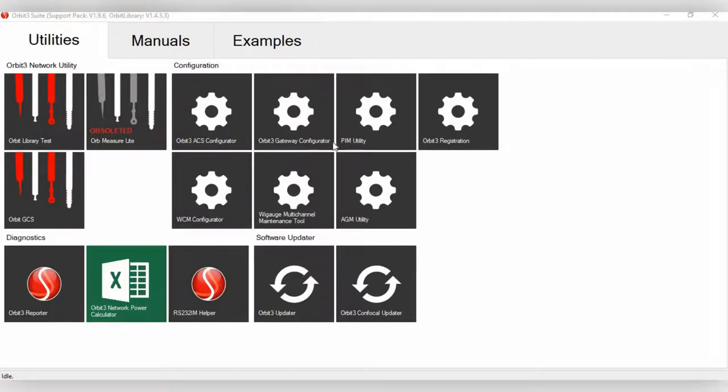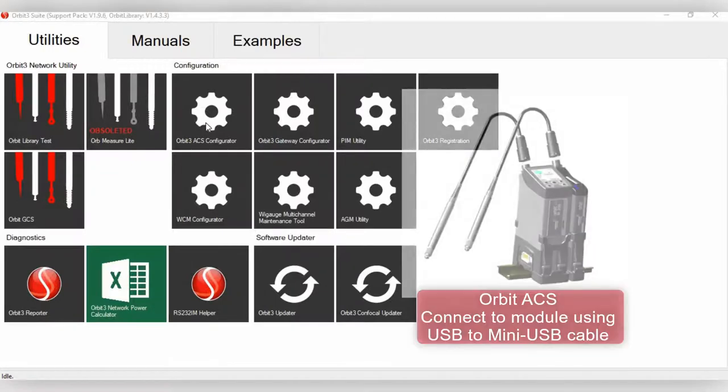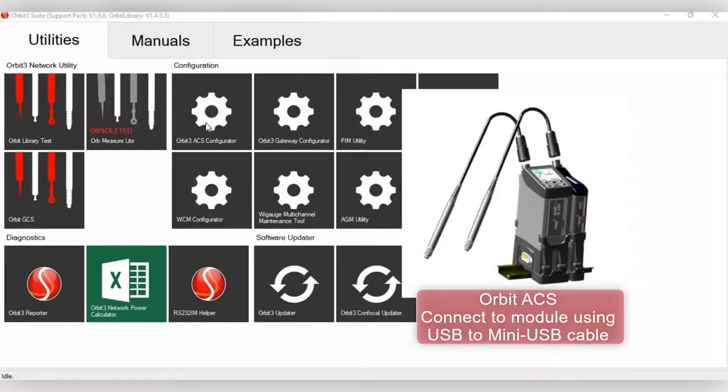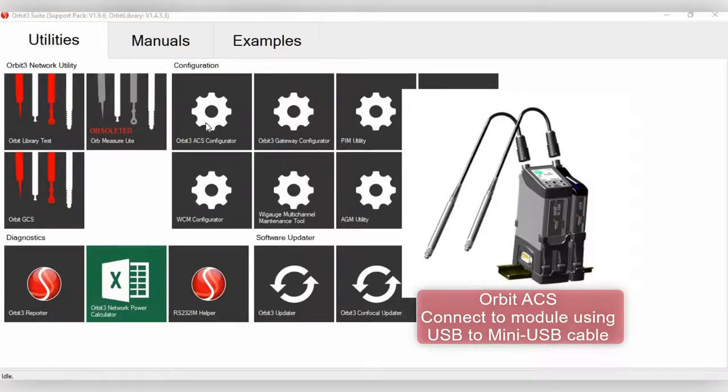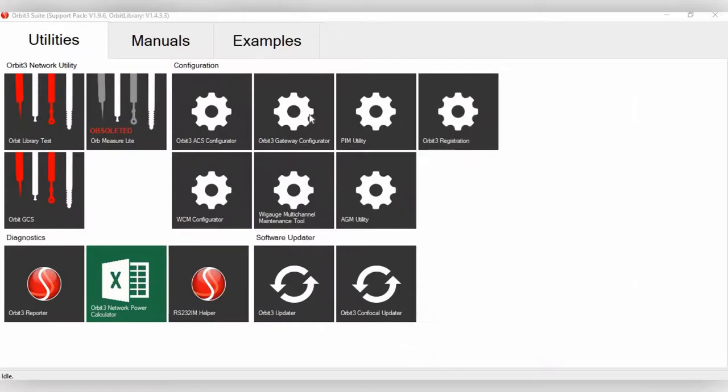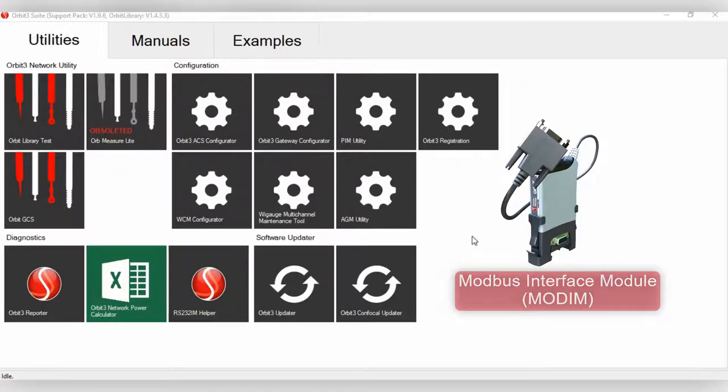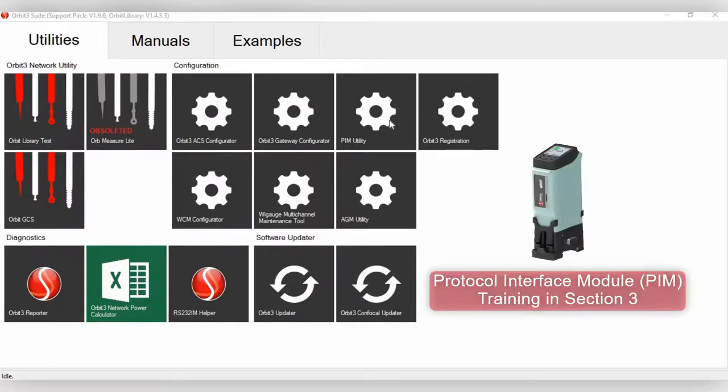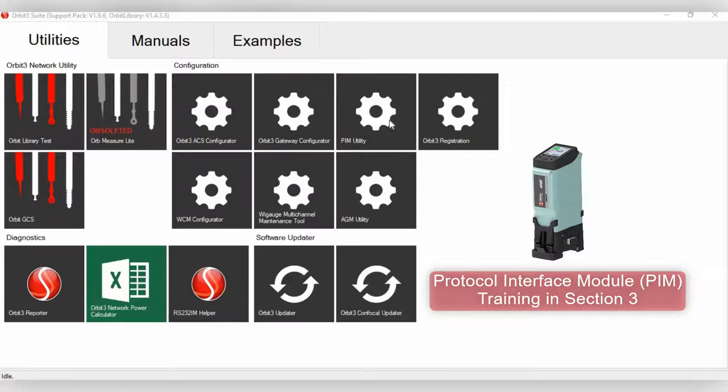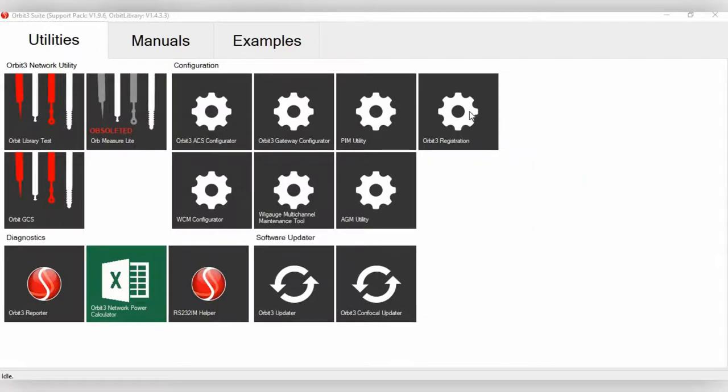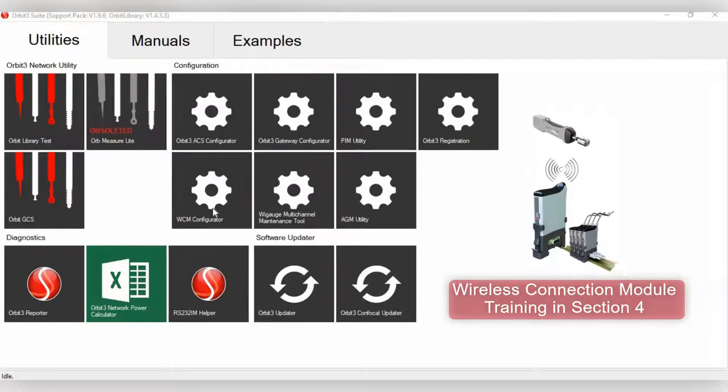Then, you know, over here, you have several configuration buttons. You have the Orbit 3 ACS Configurator. This is where if you have an SI100, SI200, or SI400 system, but you don't want to set it up on the little keypad on the main module, you can actually use this configurator to do it instead. There's also the Orbit 3 Gateway Configurator. This is for the Modbus Interface Module, which is an interface module where you are connecting to a Modbus-based PLC over RS-485 serial. Then we have the PIM Utility. This is for the Protocol Interface Module. And this, of course, is for the Gateway into Profinet, Ethernet IP, EtherCAT, as well as other PLC protocols.